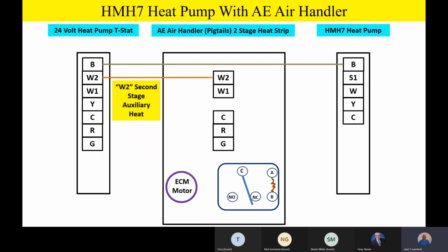If you have a two-stage heat strip, W2 from the thermostat is going to go to W2 on the AE air handler. You'll just make it up in that pigtail, your W2 on your thermostat to your indoor product. W1 is your auxiliary heat strip, or first stage auxiliary heat. And so you're going to carry that outside as well.